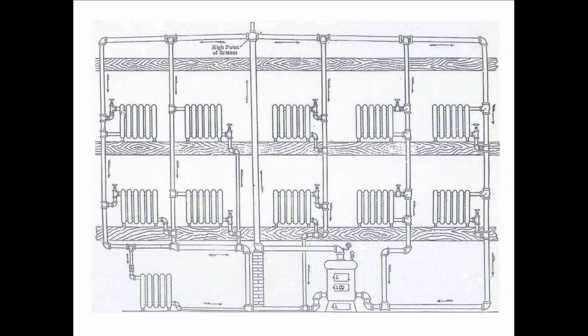So we try to come up with a way that we can have one pipe hot water heating and that brings us to this invention. This was devised by a man named Oliver Schlemmer and he was out of Cincinnati, Ohio. And he says, on this particular configuration, send all the hot water up to the top. Kind of like what John Mills did with his mill system on the steam end of things. But we'll first send all the hot water up to the high point of the system. There's going to be an expansion tank there in the attic. And then we're going to down feed as the cold water falls. The hot water will work its way down following the cold water. And now you've got the beginning of modern hot water heat.